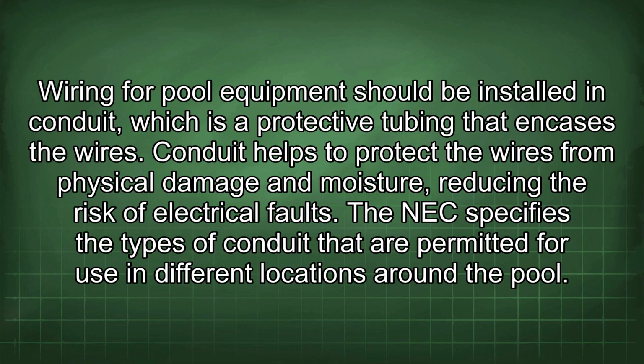Wiring for pool equipment should be installed in conduit, which is a protective tubing that encases the wires. Conduit helps to protect the wires from physical damage and moisture, reducing the risk of electrical faults. The NEC specifies the types of conduit that are permitted for use in different locations around the pool.